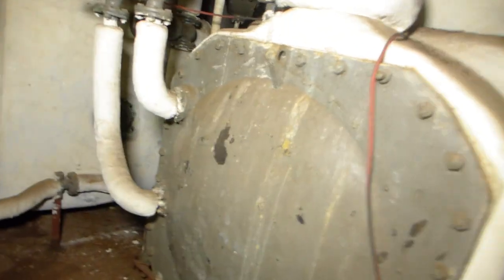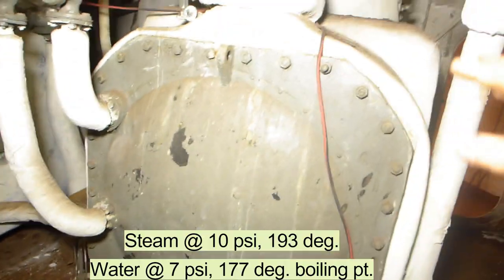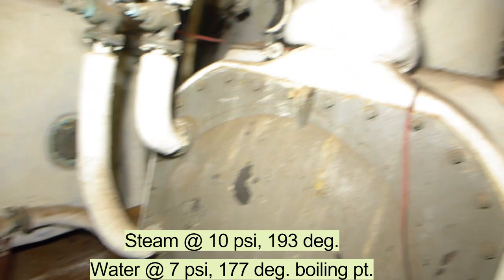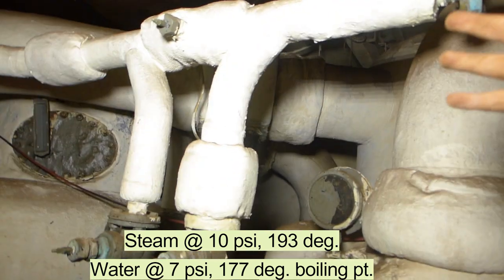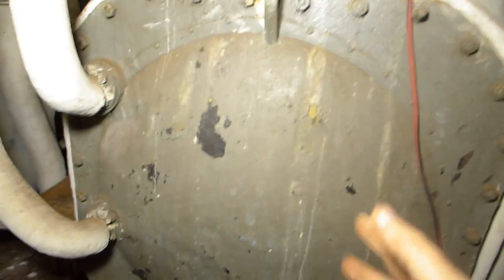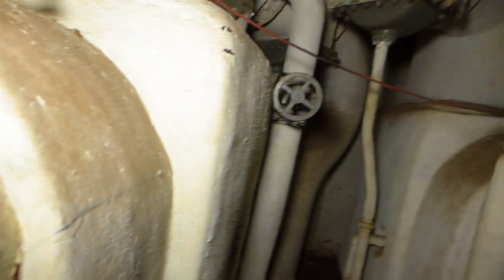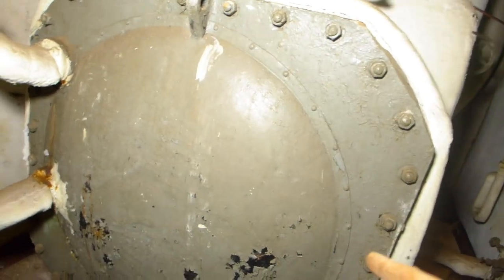Now, again, the pressure's dropped even lower. You'll see the numbers appear at the bottom of the screen for it. Again, steam condenses off of that, it comes off of that. Part of it's condensed, returned as fresh water. And then the more concentrated brine is now pumped into the third effect, where again we go with residual steam that comes off the dome of the second effect to put through the tubes that heats this last stage.